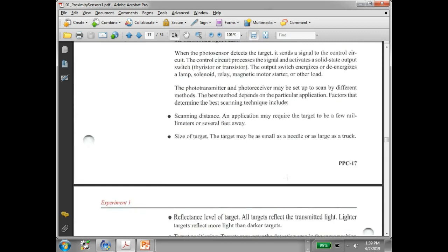So here we're going to move to our photoelectric sensor, direct scan, which is what we call through the beam. So the person calls it direct scan. Most of the time you'll see on the test when we talk about this guy, I'll use through the beam and then I'll put direct scan. So how does direct scan work? The receiver. If this guy is not detecting anything, its output will be true, right? So this circuit's going to be outputting 120 volts on our circuit. And then when the device breaks the beam, it should do what? It should cut it off.